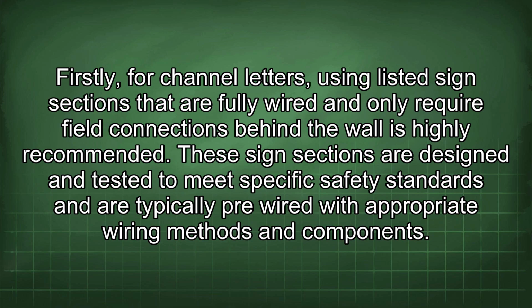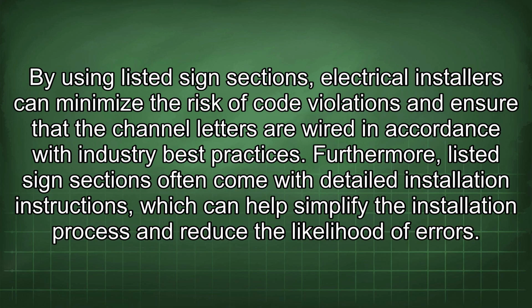Firstly, for channel letters, using listed sign sections that are fully wired and only require field connections behind the wall is highly recommended. These sign sections are designed and tested to meet specific safety standards and are typically pre-wired with appropriate wiring methods and components. By using listed sign sections, electrical installers can minimize the risk of code violations and ensure that the channel letters are wired in accordance with industry best practices. Furthermore, listed sign sections often come with detailed installation instructions, which can help simplify the installation process and reduce the likelihood of errors.